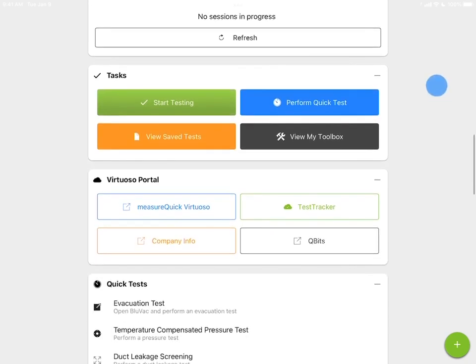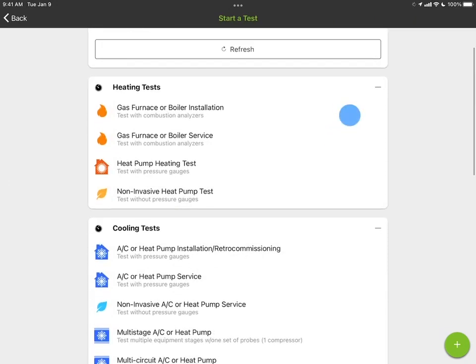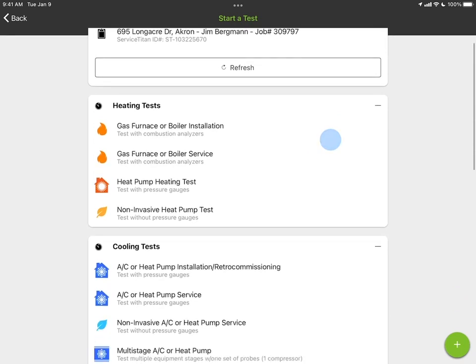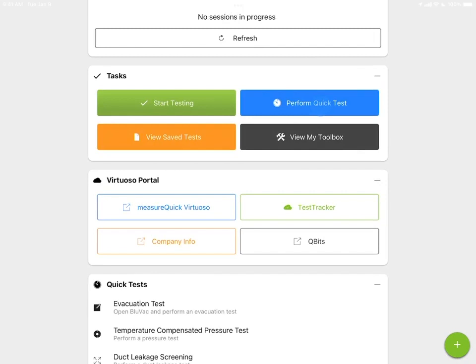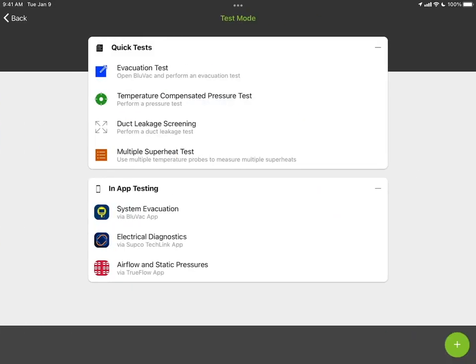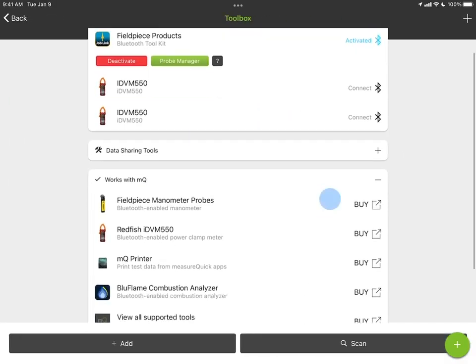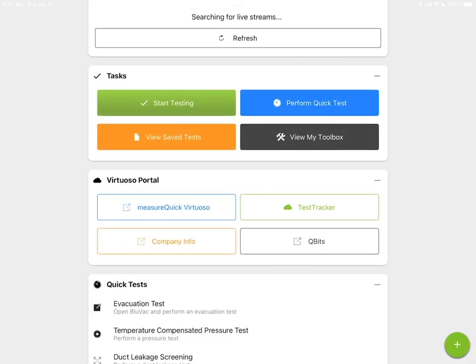Tasks is basically four different buttons that allow you to do things like start testing, perform a quick test, view your saved tests, and view your toolbox. When you hit start testing, it pulls up the types of tests — heating or cooling tests, dispatch tests, and so on. Quick tests give you access to things like the evacuation app, BluVac app, temperature compensated pressure test, duct leakage screening, and multiple superheat mode — right at your fingertips. You can also view saved tests stored on your device or view connected tools in the toolbox.